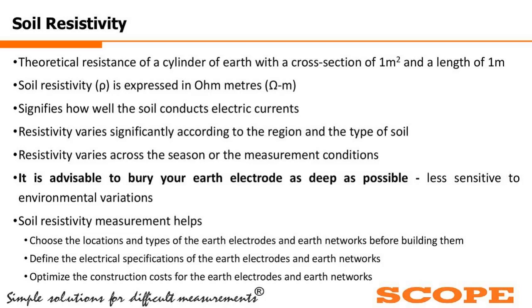Now, as we have understood, the deeper we take the earth pit rod, the better. It is advisable to bury your earth electrode as deep as possible, because it becomes less sensitive to environmental variations. Say I have put in only 50 centimeters, and some person comes with a bucket of water and pours it, the value of that resistance will immediately change. But when the electrode goes 3 meters deep, absorption of the water will take time, so it will not change abruptly.